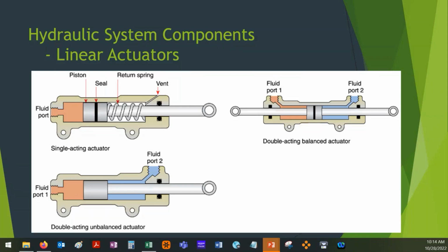Here's a single acting actuator. It's going to move to the left up here in the top, right? It's going to move to the left when there isn't pressure over here on the fluid side. Fluid's going to push it to the right. So fluid provides it, it's single acting fluid essentially. And in that case, a spring is going to push it back. And so then we've got our two double acting actuators here. We've got our double acting unbalanced on the left here and double acting balanced on the right.